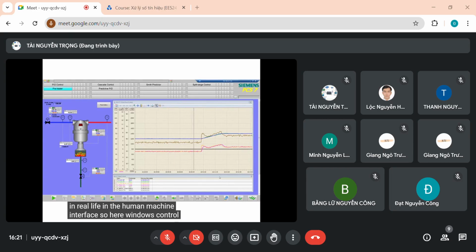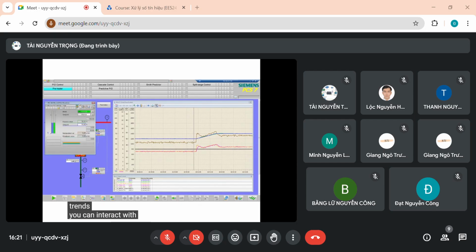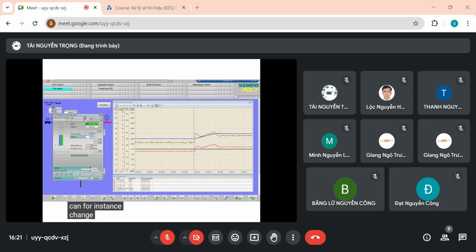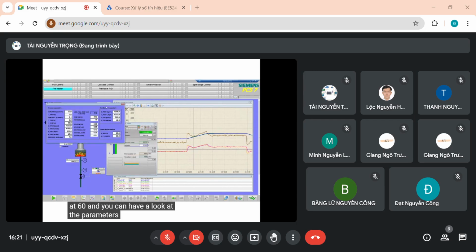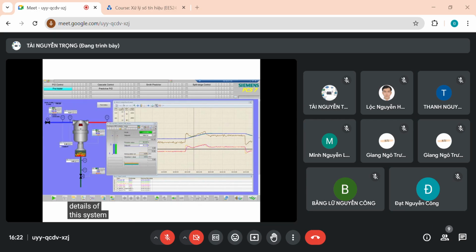So here, Windows Control Center. This is for the preheater example that we will treat later on in the course, so I will not go too much in the details, but you can see here the trends. You can interact with the system, so I can, for instance, change the set points. So you can see that the set point is decreasing here. There is a ramp on the set point, so it does not decrease directly, but you will see that it will stabilize at 60, and you can have a look at the parameters. We will not go into the details of this system for the moment. This is for later. What I want to illustrate are the controller modes that we have talked about previously.